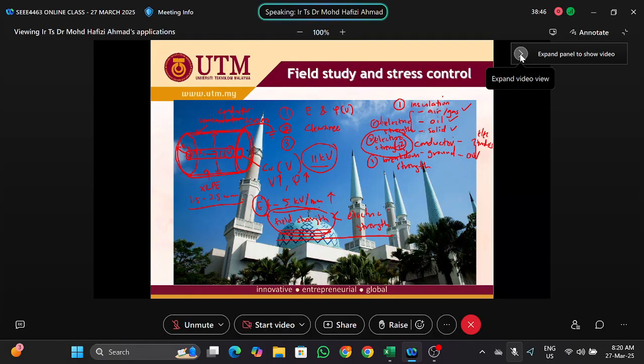Okay, so these quantities or parameters like voltage, the radius, the size, everything. And then the electric field is related to the property of the materials. So for this case we are using solid, right? So we should design the field strength to be less than the electric strength, or the dielectric strength, the material strength. So what happens if the field strength is more than the electric strength? This can cause premature failure, the partial discharge, the inception of partial discharge.